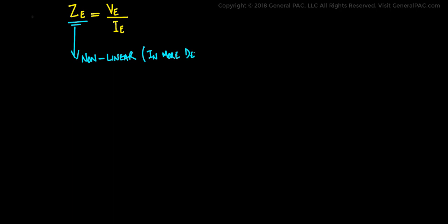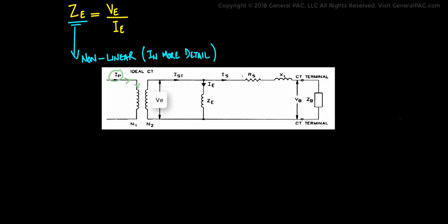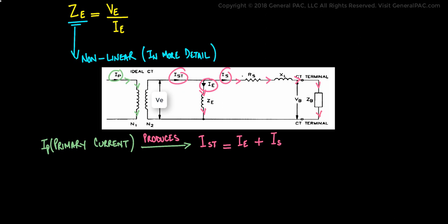Now we also have a primary current IP that flows through the primary winding of a current transformer. This IP value produces a total secondary current on the secondary side of the winding. And in mathematical terms, we can represent this parameter using the following equation. IST is equal to IE plus IS, where IE is the excitation current and IS is the secondary current flowing through the winding and flowing to the secondary CT burden.